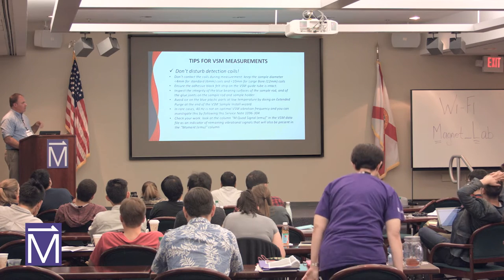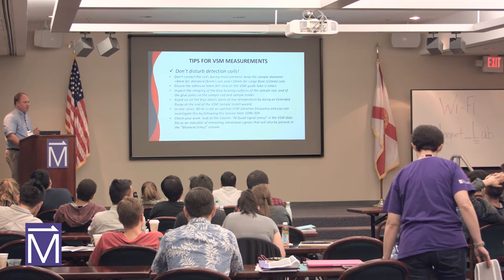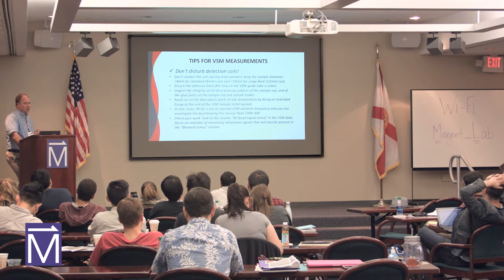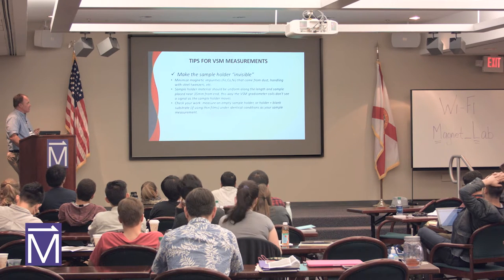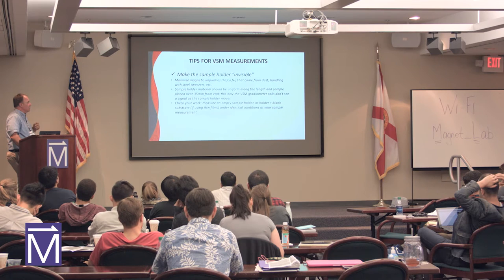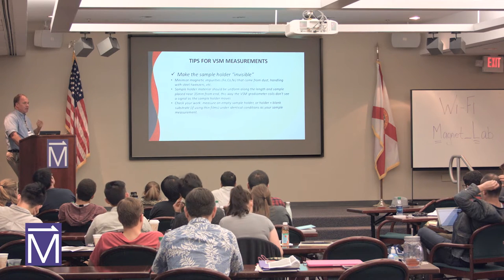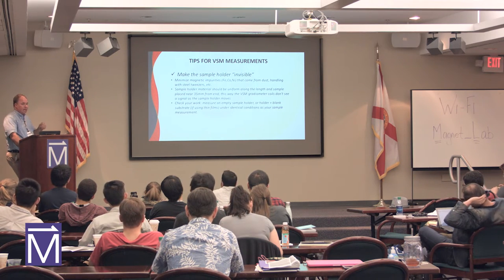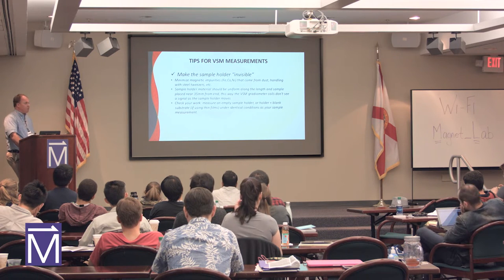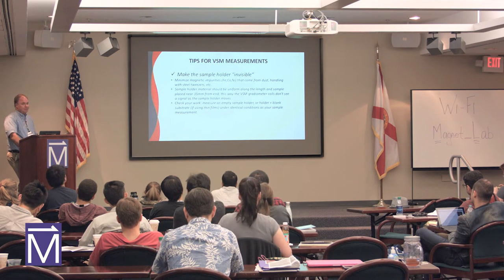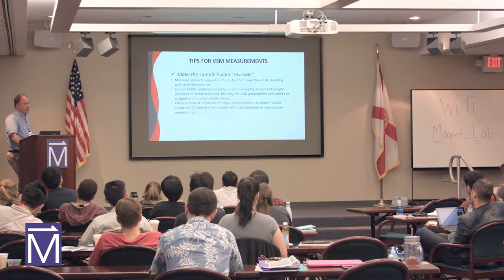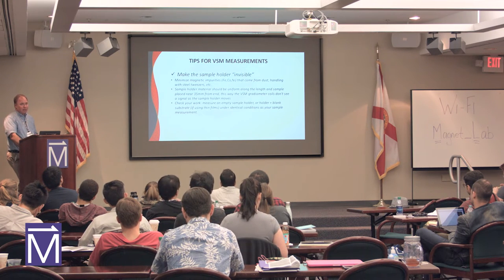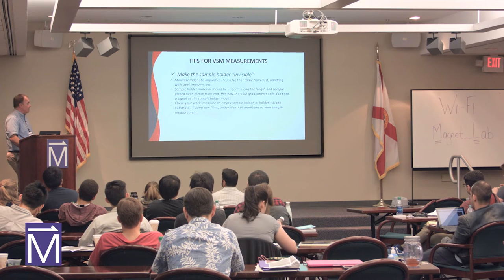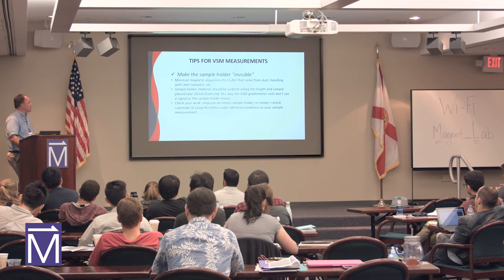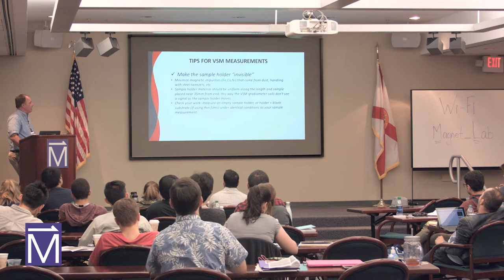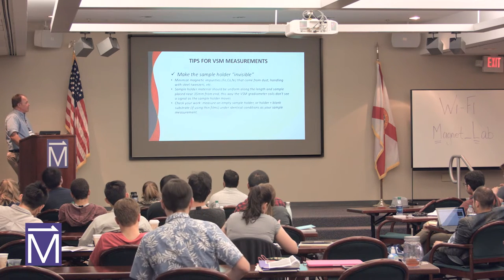There's a subtlety: if the 40 hertz frequency isn't correct, if there's some resonance, that might be an issue, and we've got an app note in the service bulletins that talks about that particular case. Make the sample holder invisible. Use non-magnetic tools when you hold your sample, because those things may add contamination to your sample, right? There are some well-known papers where people made measurements and thought they had a discovery, but it was from the tools they used, which introduced contamination into some of the nanomaterials they were developing.